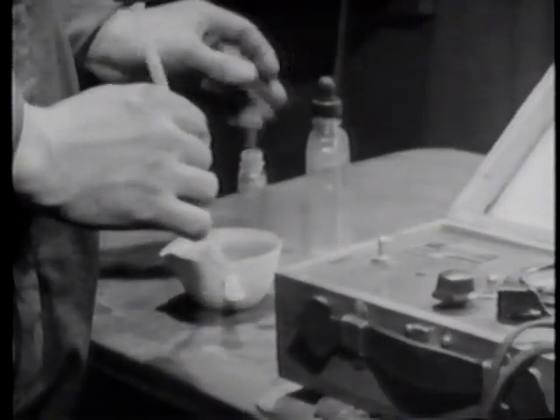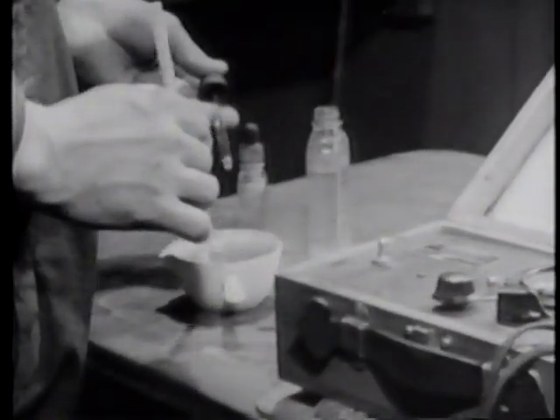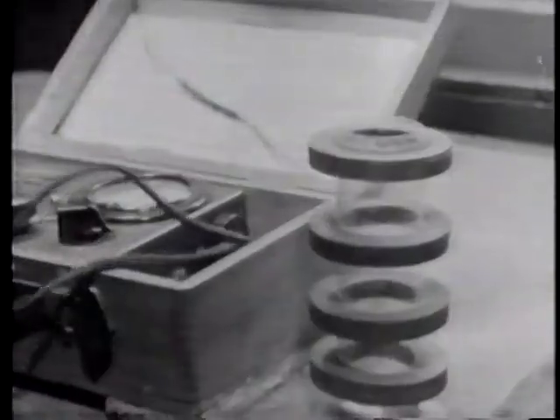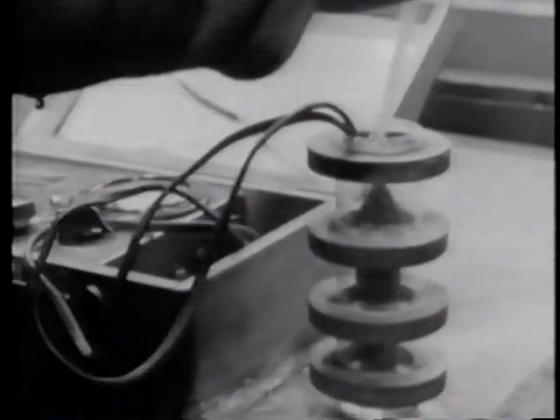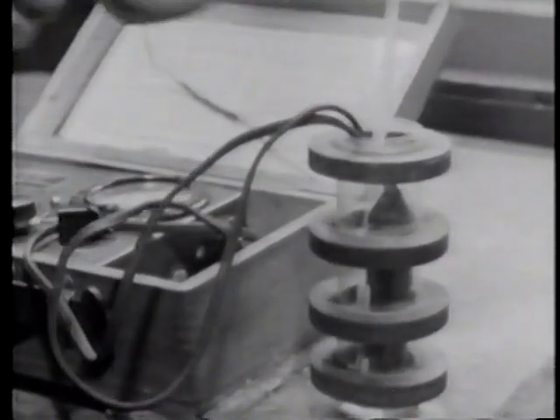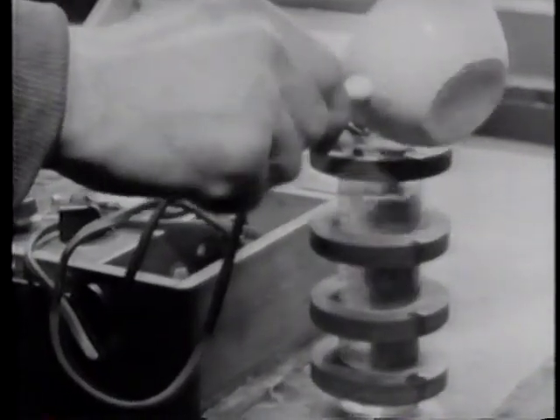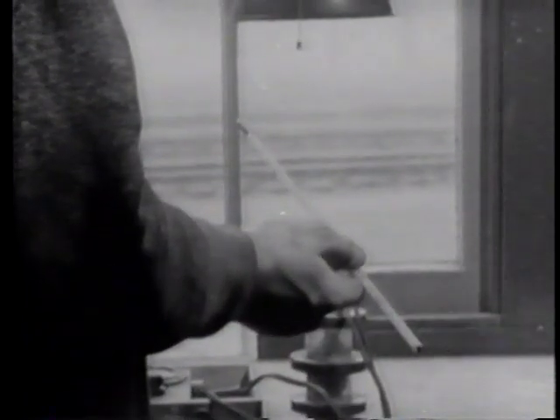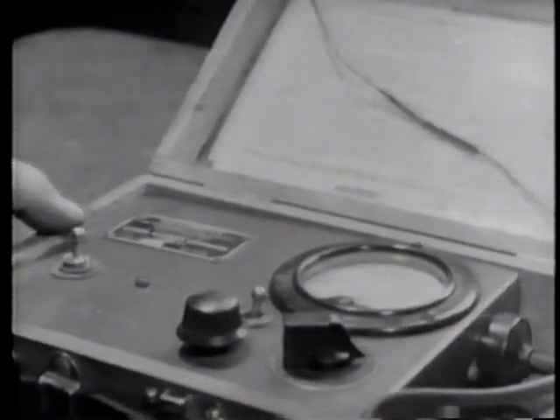A sample of water from each incoming locomotive is tested to determine the amount of dissolved or scale-forming solids in the boiler. If the proportion is too high, it is necessary to change the water in the boiler to prevent foaming and poor steaming. All water used by locomotives is treated to keep scale formation to a minimum.